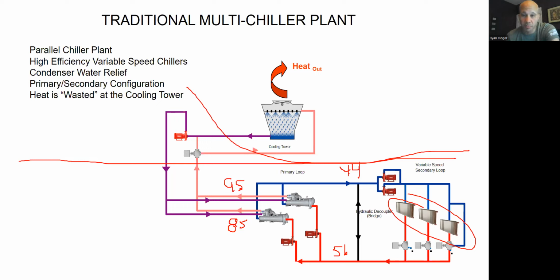We have to have all the same components we had over here. So we have to have a circulating pump. We have to have water strainers and those kind of things over here. We send this water out to the cooling tower. And then for most cooling towers, we take that water and we mist it into the outside air, and we blow air across it, or we suck air. In this case, it's a draw through. We suck air across it for this particular design of cooling tower. And when we do that, that has a cooling effect on the water.